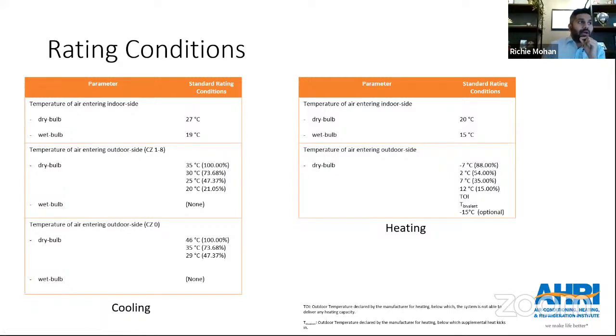And on the outdoor side, we are going to have a full load and a part load rating condition, and there's a load line for heating as well, which is shown in this particular cell of the table, where you will basically go all the way up to 88%, where the corresponding outdoor ambient temperature is -7 degrees Celsius. And you will go as low as 15% of operation in the part load mode, with a corresponding temperature of 12 degrees Celsius.